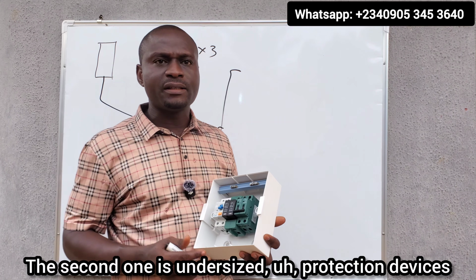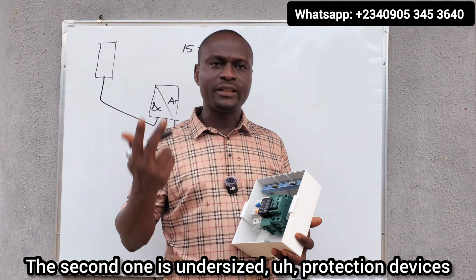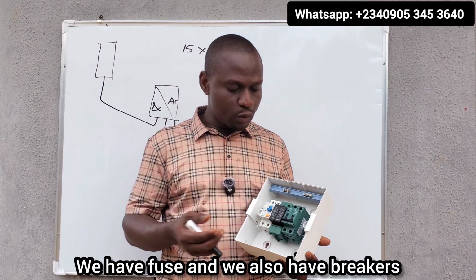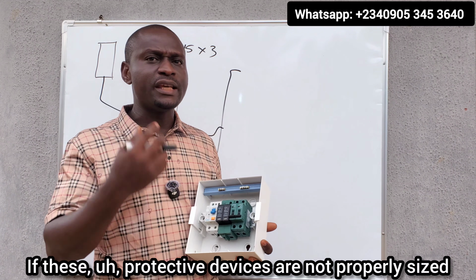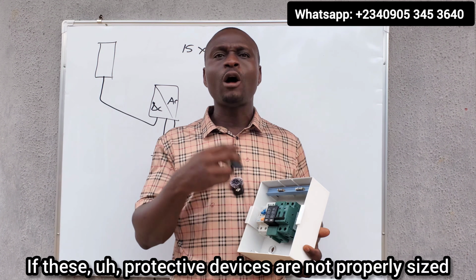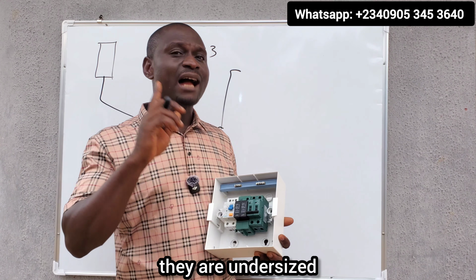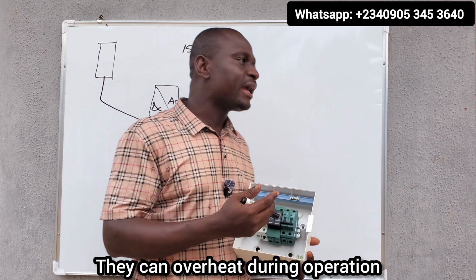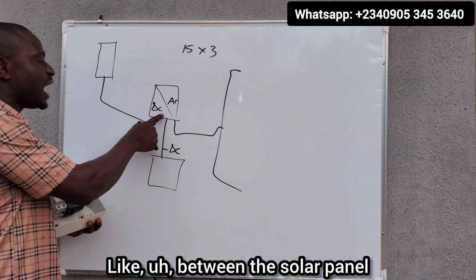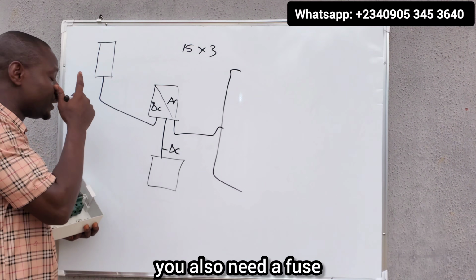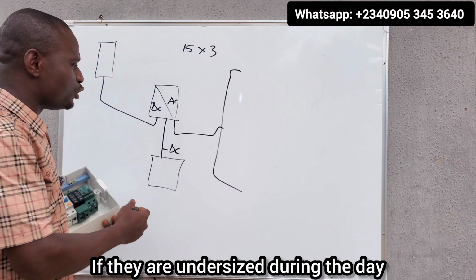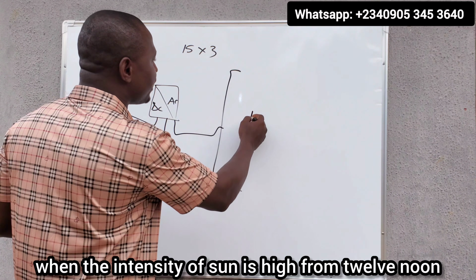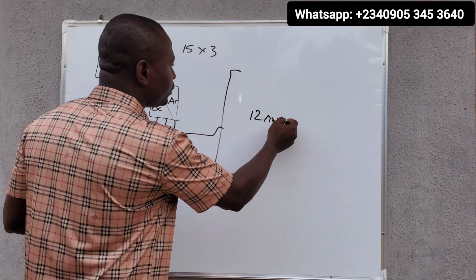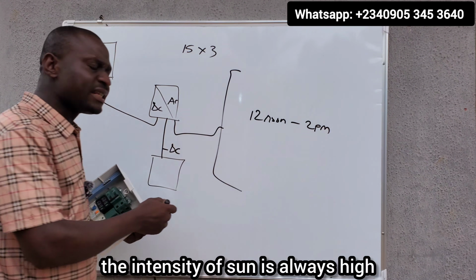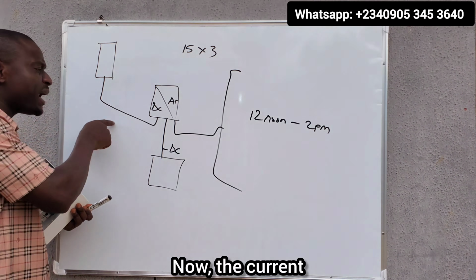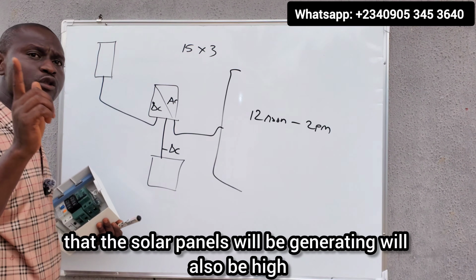The second one is undersized protection devices. We have fuses and we also have breakers. If these protective devices are not properly sized, they are undersized, they can overheat during operation. Like between the solar panel and the inverter, you need a breaker, you also need a fuse. If they are undersized, during the day when the intensity of the sun is high, from 12 noon to maybe 2 p.m., the intensity of the sun is always high.